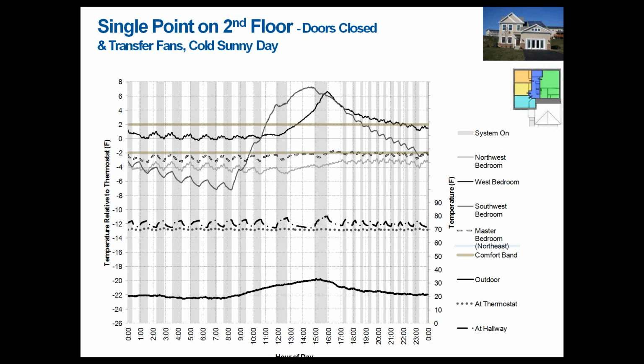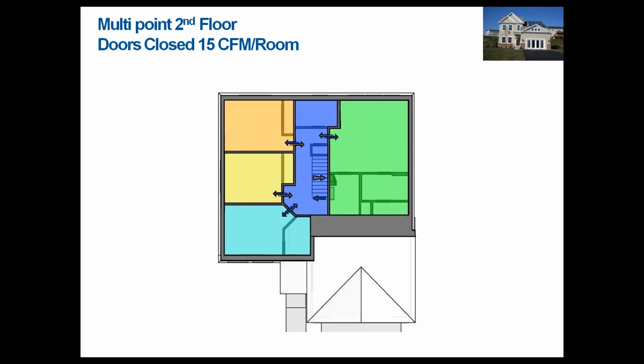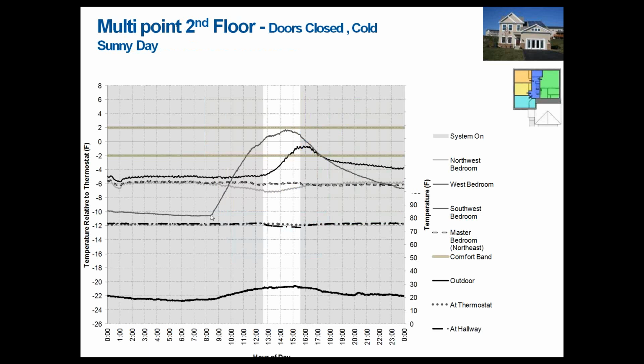So another case that we then looked at was to supply a very limited CFM to each of the rooms on more of a consistent basis and see if that, in effect, could condition the rooms without a full duct system. In this case, we used a very small diameter 2-inch pipe to deliver that air. And despite that continuous operation, we still saw problems during cold, sunny days with overheating, that it just wasn't mixing well enough. So this continues to be a problem that we're seeing, is houses that have a lot of glazing tend to overheat. And so there's different strategies you might be able to use, such as shading, that would help reduce this impact.